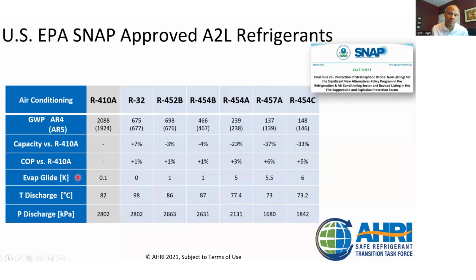And unfortunately, it's expressed in Kelvin on this chart, which none of us have our minds wrapped around. But for normal evaporator temperatures for 454B, it's 1 degree Kelvin. That's like, I'm going to call it 2.5 degrees Fahrenheit. So refrigerant traveling through the evaporator coil, boom, right here, one of the two refrigerants inside there starts evaporating, and then X number of inches later, the other one starts evaporating.